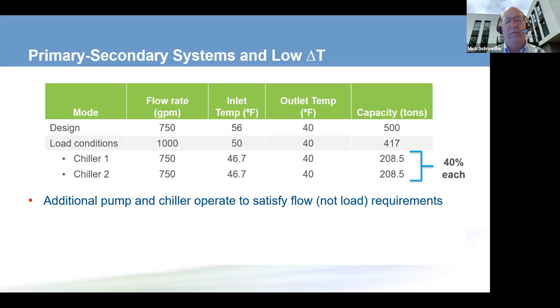We send a warmer water temperature out to the chillers, and the flow rate keeps going up and up. So in a primary secondary system, we have to turn an additional chiller and pump on. Now, although one chiller has enough capacity to satisfy the load, we don't have enough flow to satisfy the load. So when we turn an additional chiller on, we turn another chilled water pump on. If it's a water cooled system, another condenser water pump, and likely another cooling tower fan. And we end up operating two chillers at 40% low load along with our ancillary equipment, and the system becomes inefficient. But that's about the only thing you can do in a primary secondary system.